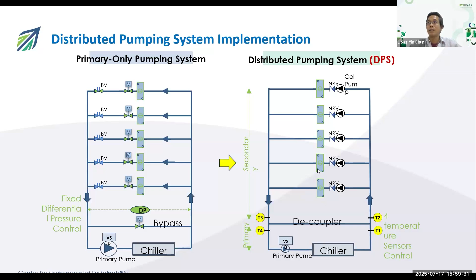So in this case, instead of a bypass, we have a decoupler, and our control strategy is to make sure there's no flow in the bypass, such that how much you pump on the primary side will be what's required on the secondary side. So there's no over pumping, and there's no under pumping as well. That's how we manage to reduce the energy required to pump the water, because we basically remove all the valves.